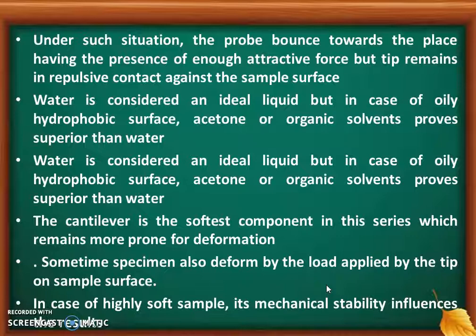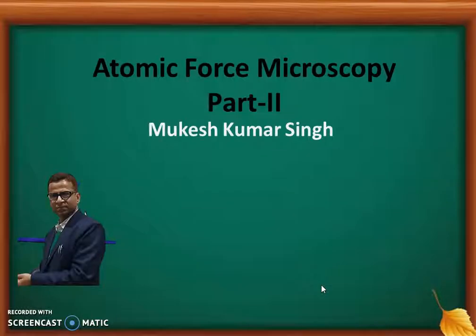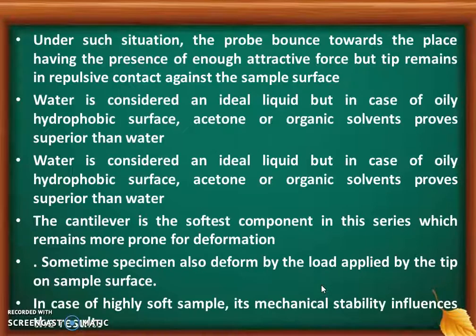The cantilever is the softest component in this series, which remains more prone to deformation. Sometimes the specimen is also deformed by the load applied by the tip on the sample surface. In case of a highly soft sample, its mechanical stability also influences the result.